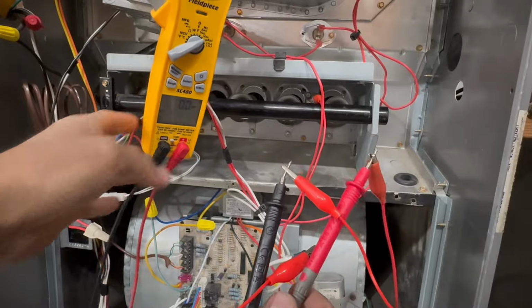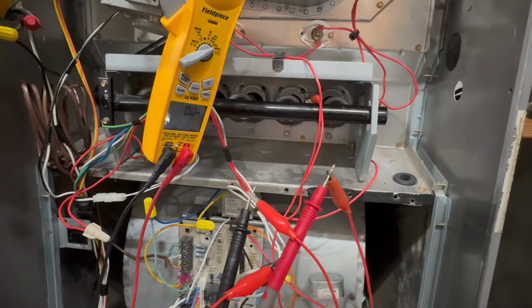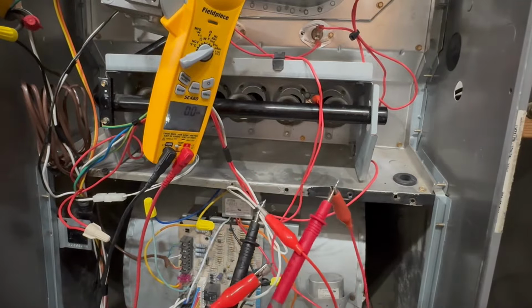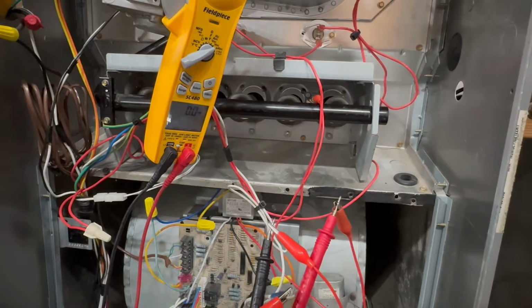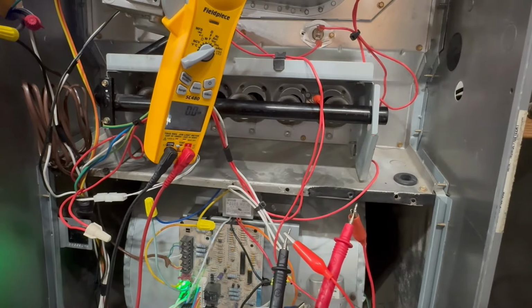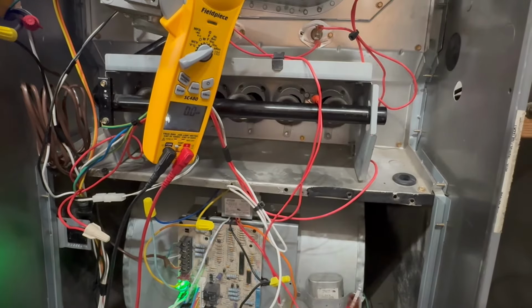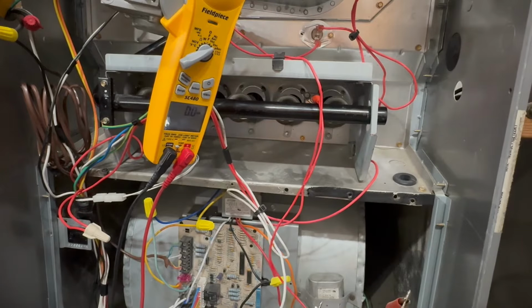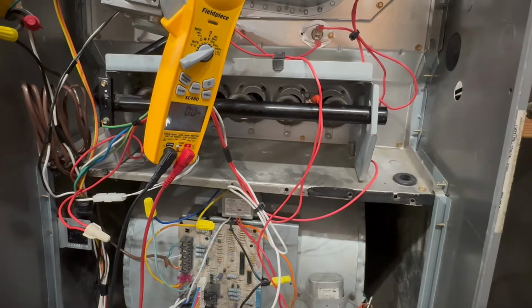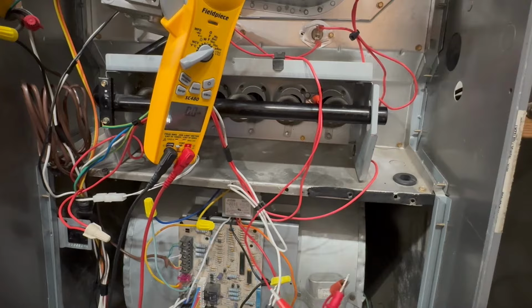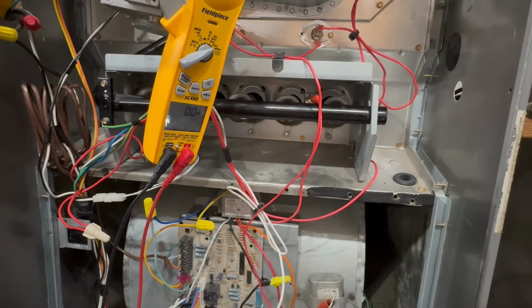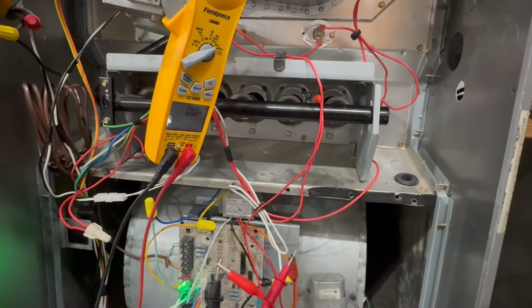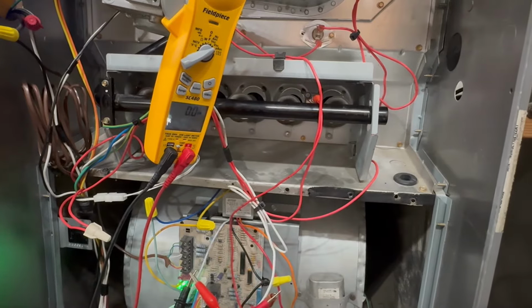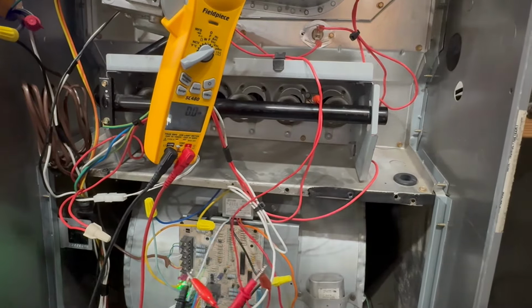I'm going to go ahead and turn it on, and we're going to call for heating. Let's see. Because I removed the flame sensor, the blower motor turned on because it's like, hey, what's going on? I'm not sensing any flames. But let me see if I can reset it just by disconnecting power and connecting it back. All right, I think we're good. All right, there we go.